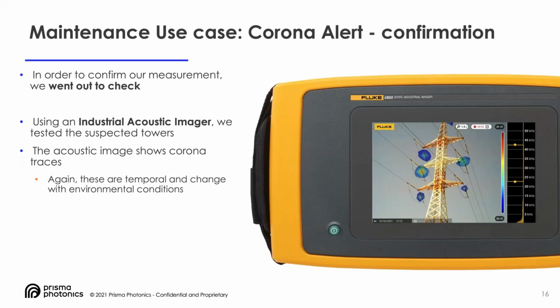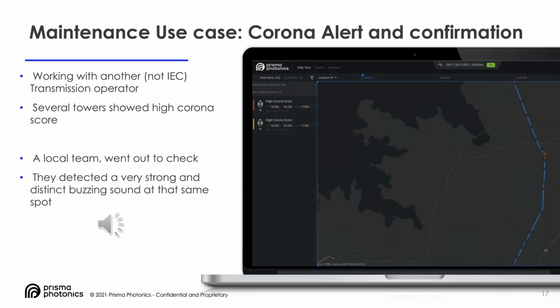In order to validate it, we did a confirmation: we took a measurement device, went out, and checked the towers that had high scoring. In real time we could compare the sensor or camera readout with the system readout and validate towers exceeding or beyond the threshold. We also validated this measurement on another line, not the Israeli Electric Corporation's, but another transmission operator's, just to confirm the results.